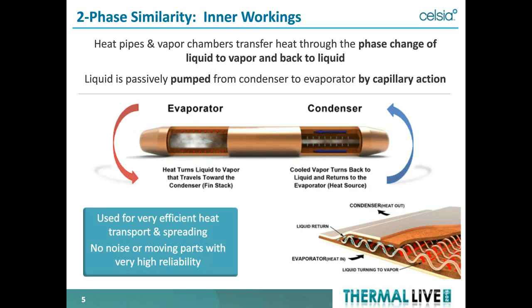These devices are vacuum devices, so they do work below the working fluid boiling point. The key takeaway is that the limit to the performance of these devices is usually the capillary limit — getting the fluid returned back to where the heat is taking place.